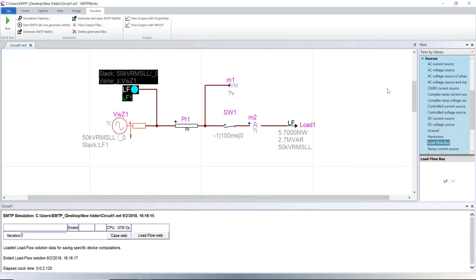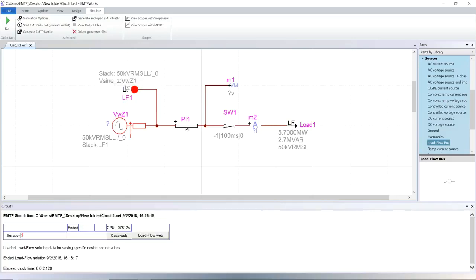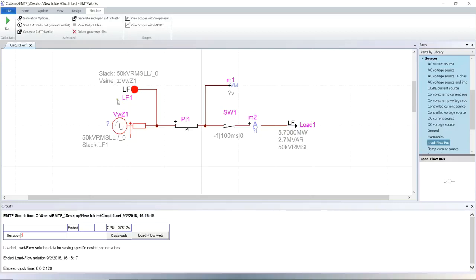The only difference between load flow and steady state calculation is in the participation of load flow devices and standard source devices. During load flow calculation, load flow devices go into the load flow solution, while the standard source devices that they are linked to are inactivated. During the steady state and time domain solutions, it is the opposite.